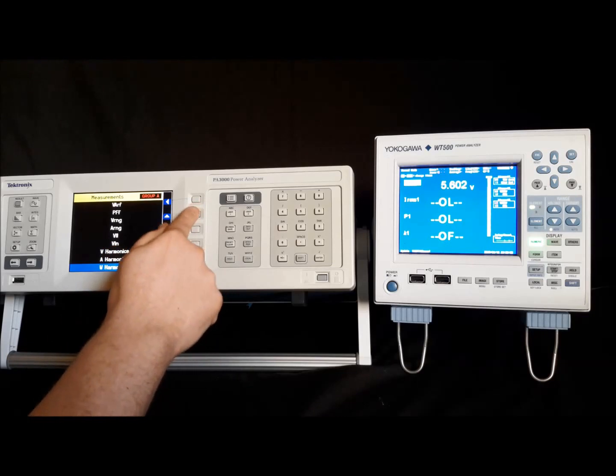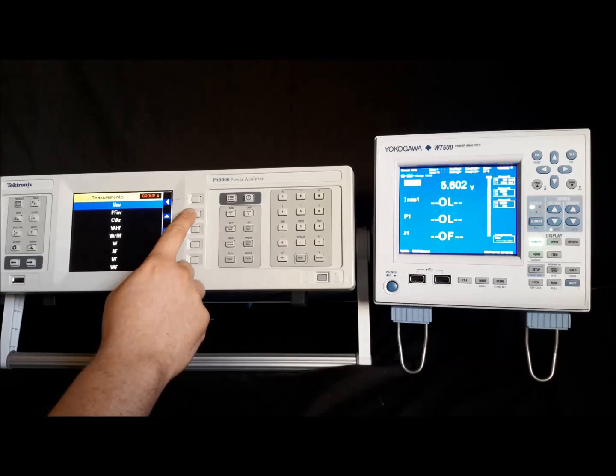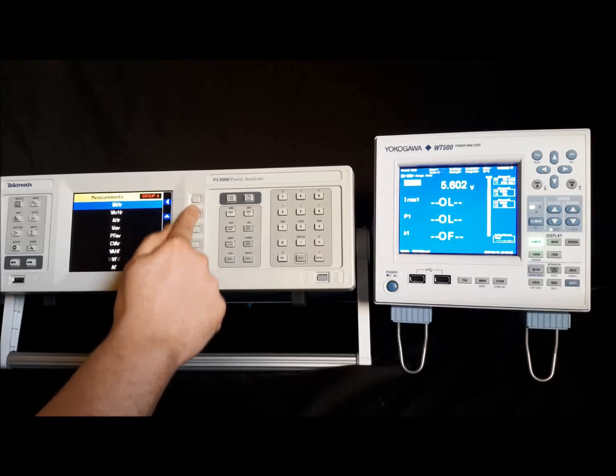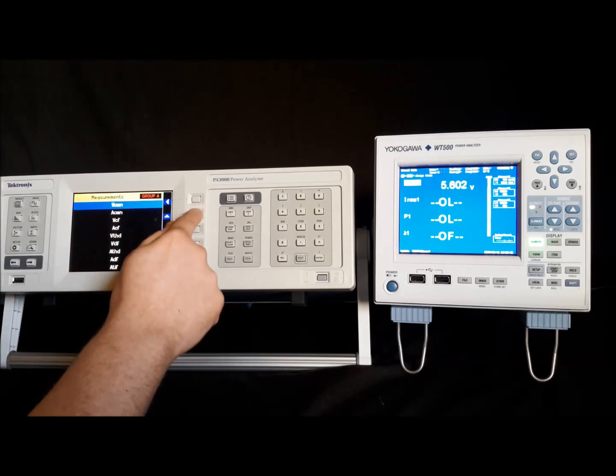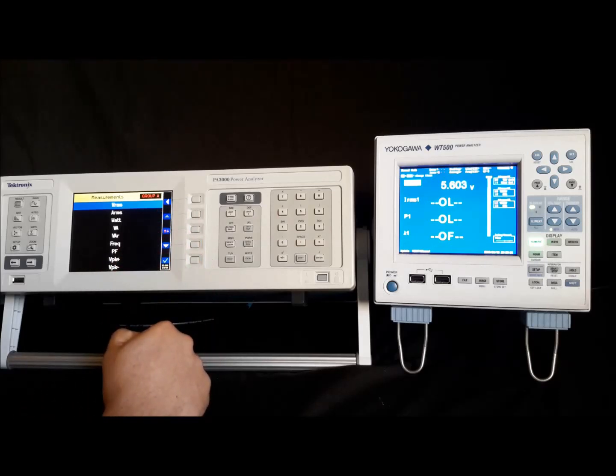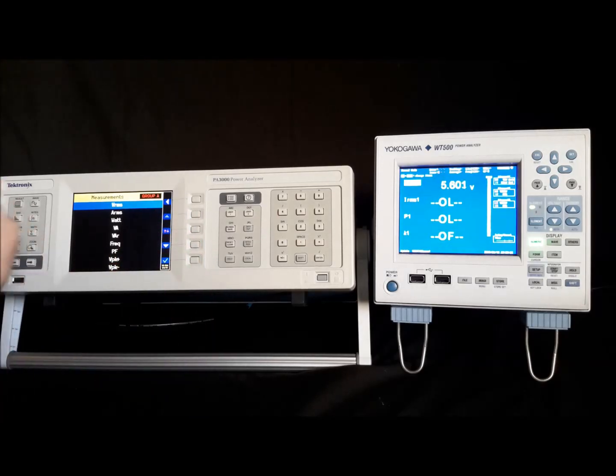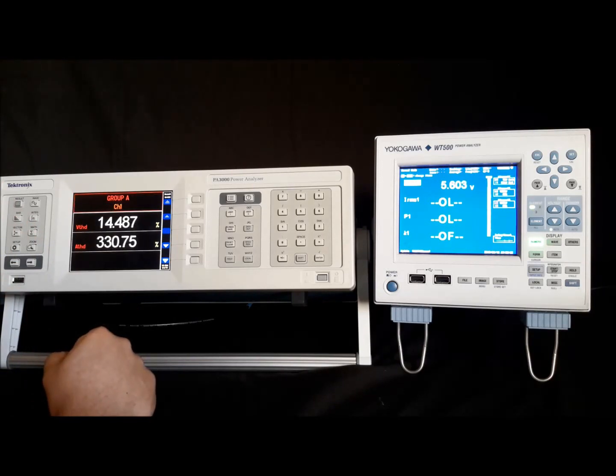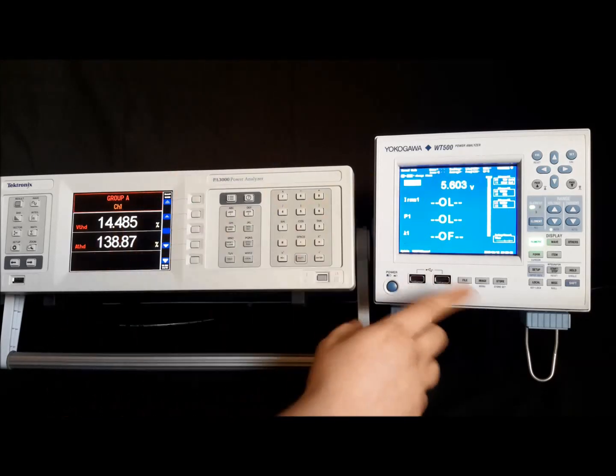Okay, no, there's individual harmonics. I want to look at THD. So I can't find a power THD. Just amps THD, volts THD. Okay. Nothing that's telling me that there's a watts THD reading on there. Okay. Okay, that's a first, something that's above 100%. Let's see what the Yokogawa says.